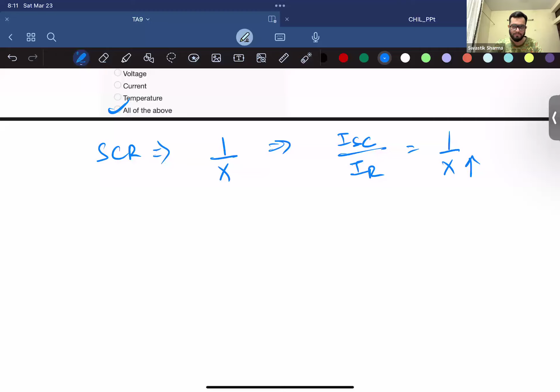You can see online in some papers where they have mentioned the strength of the grid. And one more thing, it's not just the short circuit ratio, it's also that if the impedance is more, the voltage regulation in the system will also be poorer. Since the impedance is more, the drop in the voltage would also be more, right? So there are multiple reasons why the short circuit ratio, which is 1 upon X, should be as high as possible. But the minimum value, I don't have. Generally, for synchronous based systems integrated to the system, the ISC should be at least 5 times the rated current, right? So you can see what could be the best alternative for you.